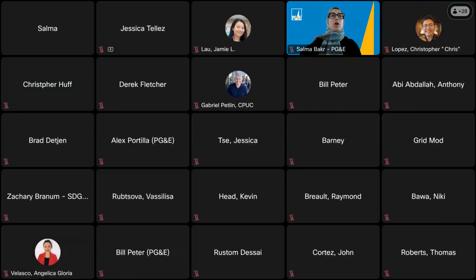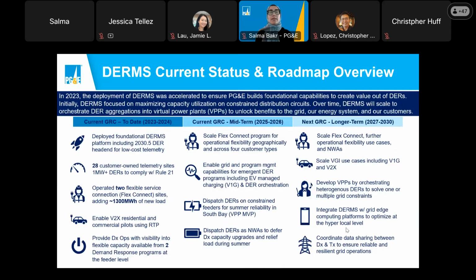Thus far, we've deployed our DERMS platform, including a DER headend for IEEE 2030.5. To comply with Rule 21, we've deployed 28 customer-owned telemetry sites for DERs 1 megawatt and above. The first operational flexibility use case we've deployed is our Flexible Service Connection Program, or Flex Connect, where DERMS provides customers with operating flexibility above their planning limit.